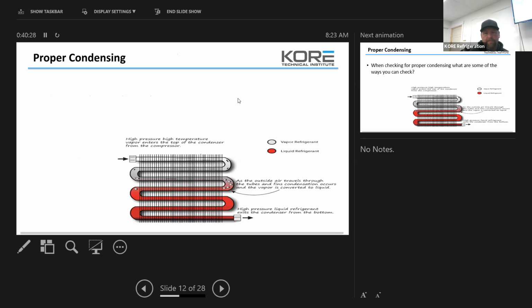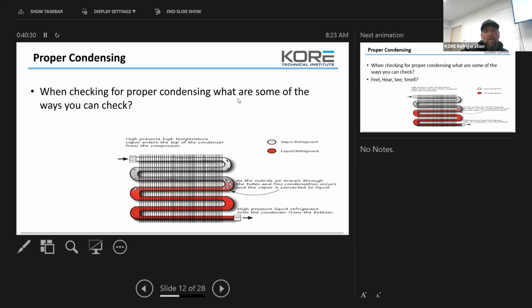Proper condensing. When you check for proper condensing, what are some of the ways you check? What's the first thing we can do to check proper condensing? It's an easy one. Touch the liquid line, right? The liquid line will tell us it should be a little bit warmer than ambient temp. A little bit warmer, not hot.